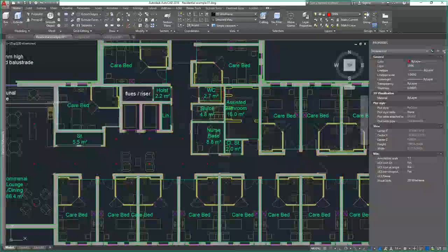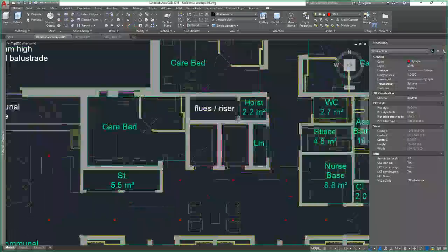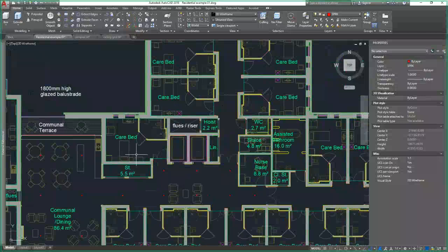In some instances, like this room here, for example, is an odd-shaped room. We could have 3 heads, I guess, with 2 of the heads being at an angle. And you've got to ask yourself whether the advantage in saving a sprinkler head is worth the compromised aesthetic of having sprinkler heads at weird angles within the room. I would say it isn't. Stick an extra head in, keep them in nice neat rows.